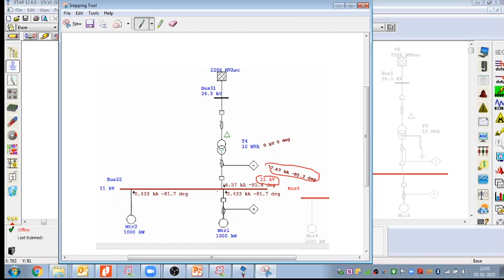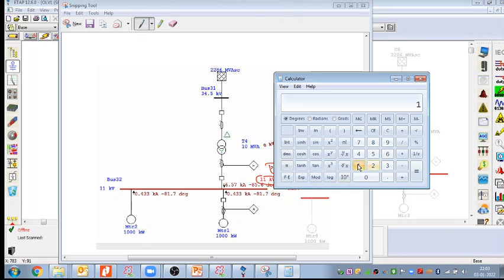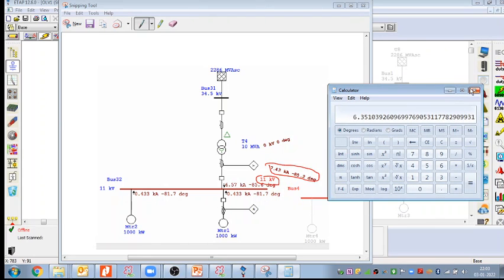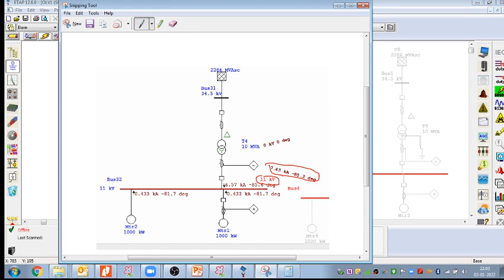So on this the voltage should be 11 divided by root 3, right? As per the calculations, this should be 11 divided by 1.732, which comes to around 6.4. This should be around 6.4, but it has jumped to 11 kilovolt. But yes, the fault current is coming here. So this is the drawback of the ungrounded system: the phase voltage jumps to the line voltage. But whether a system is grounded or ungrounded, the three phase fault current remains the three phase fault current. It is not going to change any value.